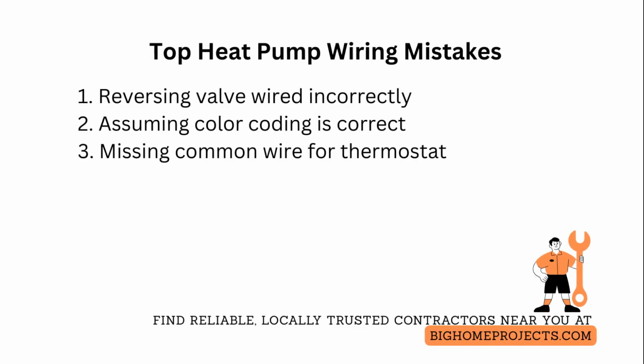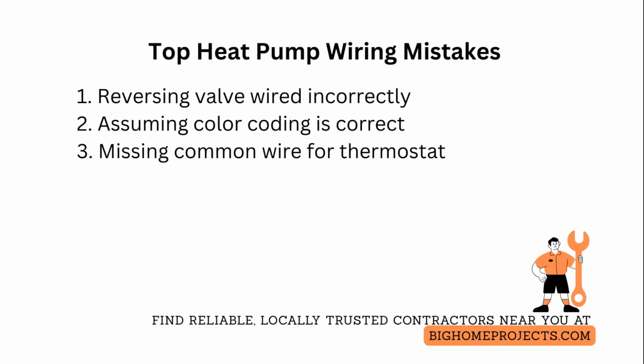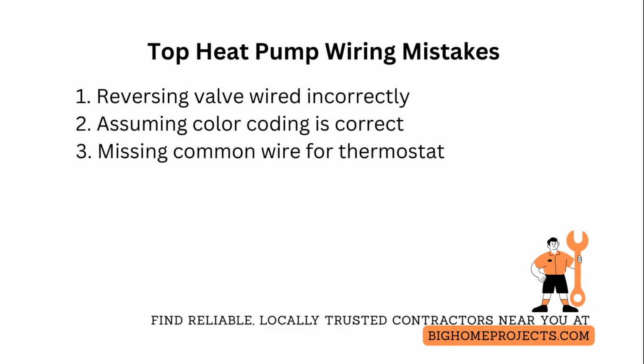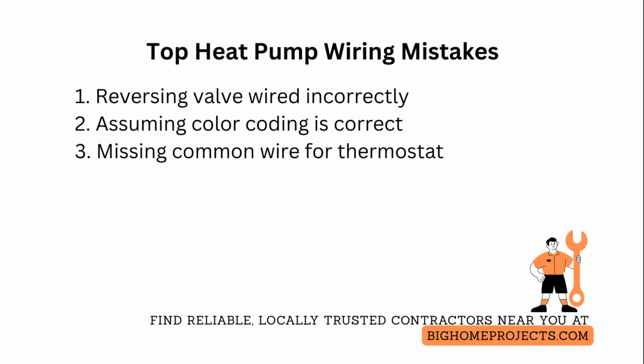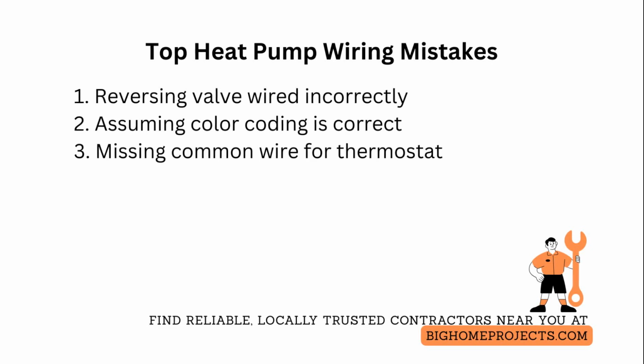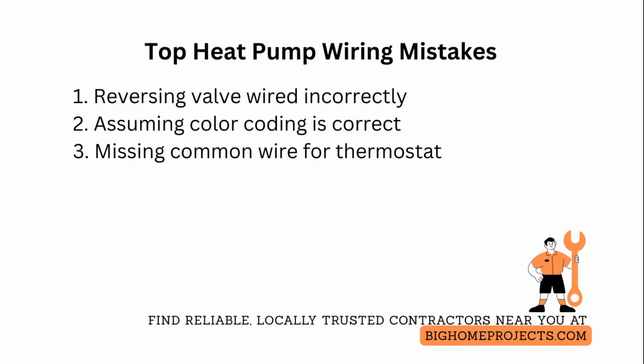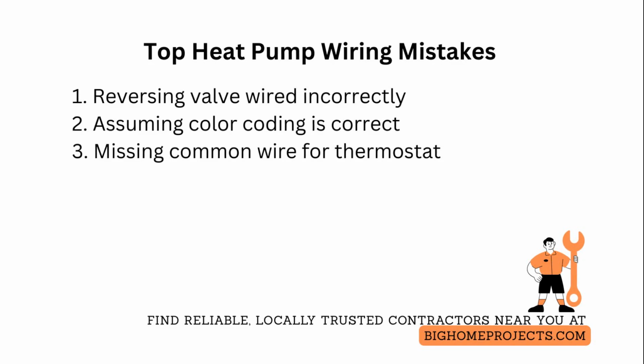Fix this by powering the system in test mode and confirming reversing valve behavior or swapping the valve lead after confirming wiring labels. One of the top errors is assuming color coding is correct and not tracing wires, leading to fan or compressor powered unexpectedly. Remedy that by labeling both ends and using a continuity tester to verify each conductor before connection.